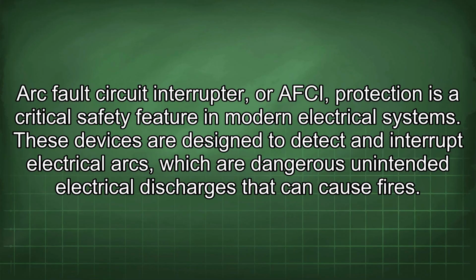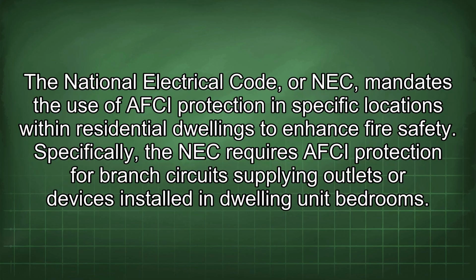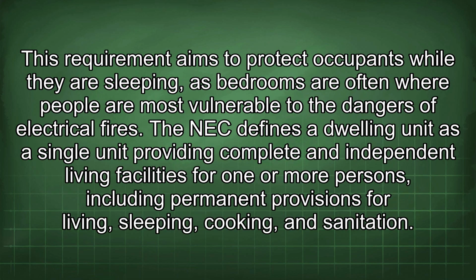Arc fault circuit interrupter, or AFCI, protection is a critical safety feature in modern electrical systems. These devices are designed to detect and interrupt electrical arcs, which are dangerous unintended electrical discharges that can cause fires. The National Electrical Code, or NEC, mandates the use of AFCI protection in specific locations within residential dwellings to enhance fire safety. Specifically, the NEC requires AFCI protection for branch circuits supplying outlets or devices installed in dwelling unit bedrooms. This requirement aims to protect occupants while they are sleeping, as bedrooms are often where people are most vulnerable to the dangers of electrical fires.